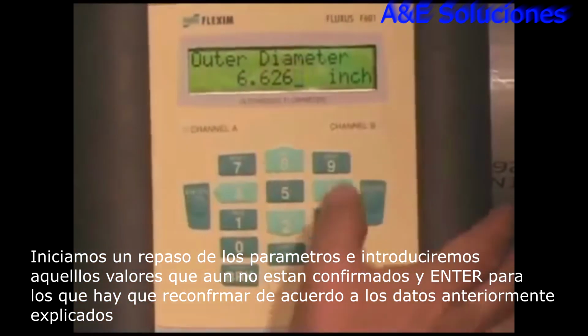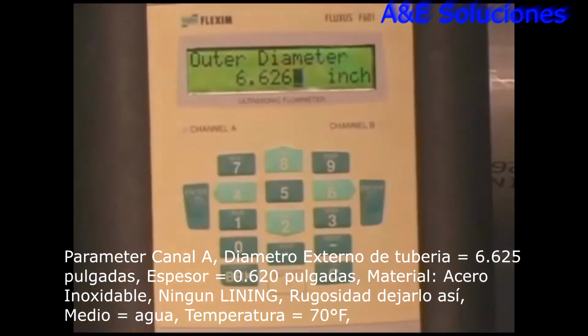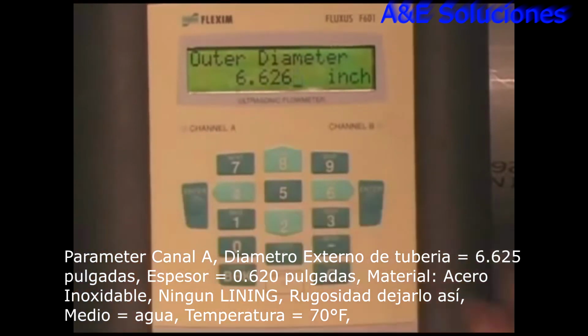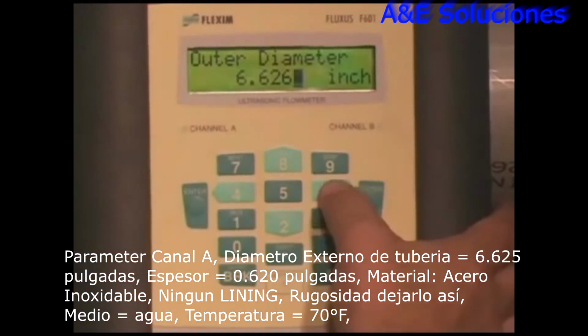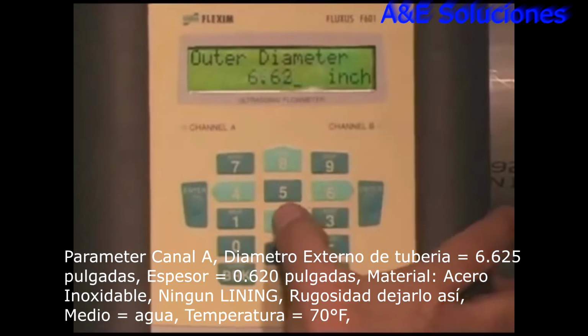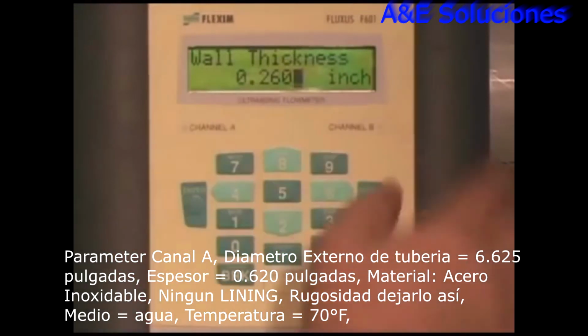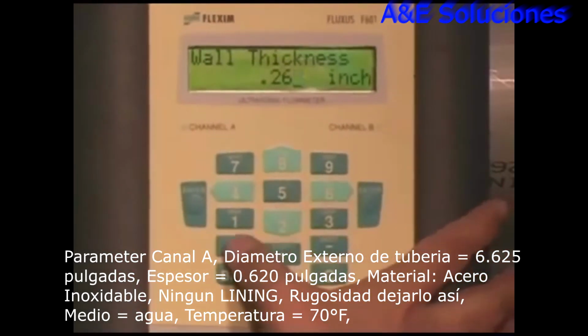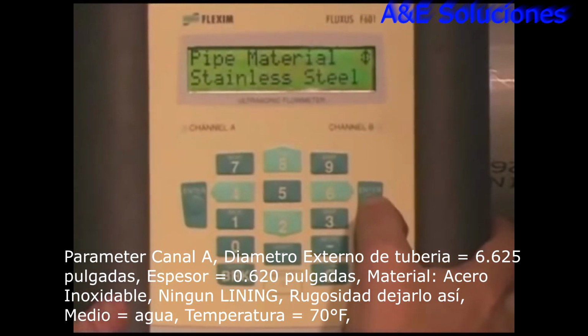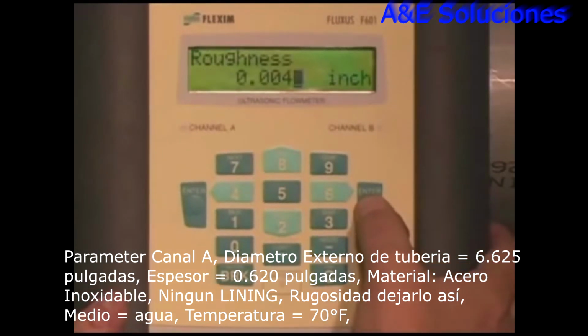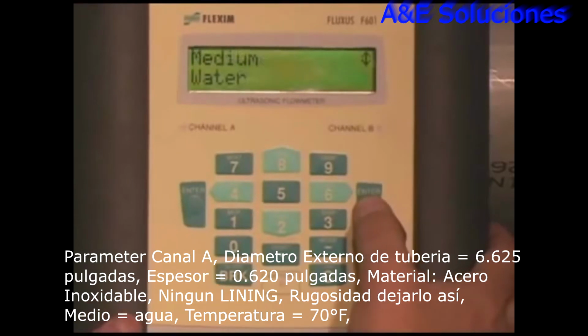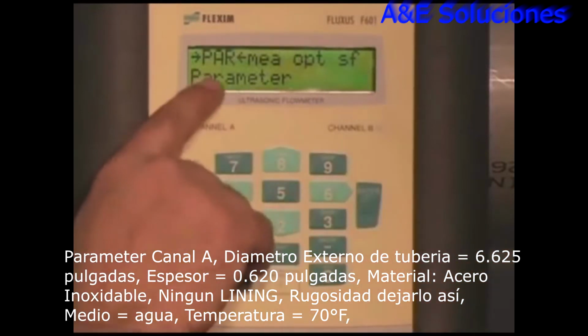I'm going to enter in my pipe size. It already has that value. If I want to, I can just hit the enter key, but just for demonstration, 6.625. I'm going to enter in the wall thickness, 0.260. The material, hit enter. No liner, enter. Roughness, leave it alone, enter. The liquid's water, hit enter. Temperature 70 degrees, hit enter. I'm done with the parameter entries.